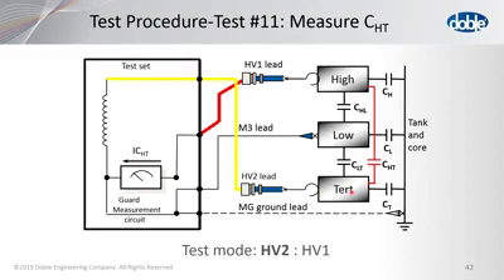So it's what we call an ungrounded specimen. Well, in a low current situation like you have here, any path to ground has a tendency to make the measurement that you're measuring go negative. It's just the physical situation that you have with the transformer. It will make the test go negative or make it go lower than it actually is. We find this quite common on ungrounded specimen tests where you have a high resistance path to ground. There's been probably 3 or 4 papers written on this. I would suggest go to the portal and read those because they're quite interesting in how that phenomenon of a negative power factor is quite common in testing.